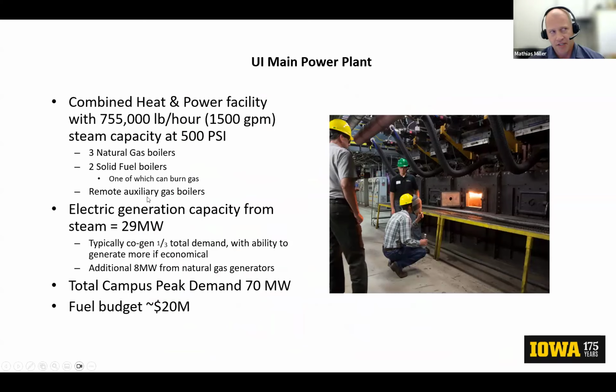Our electrical generation capacity from the power plant is 29 megawatts. As I mentioned earlier, typically we're only making about one-third the electricity that we're using on campus. What we do is kind of follow the steam load, so the steam demand out on campus drives how much electricity we're producing, because the steam on its way out is passing through the turbines, generating electricity.